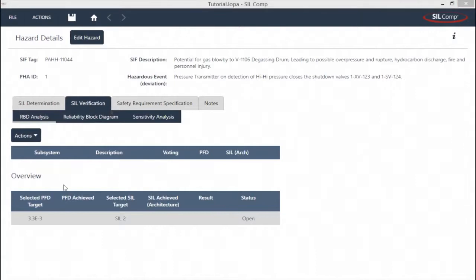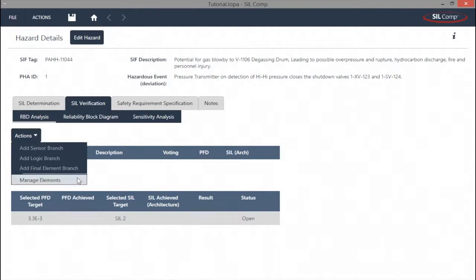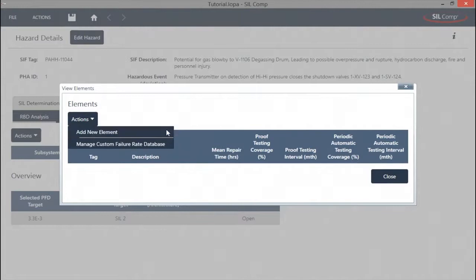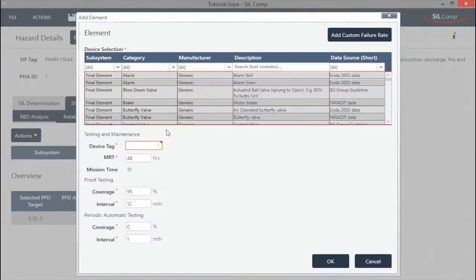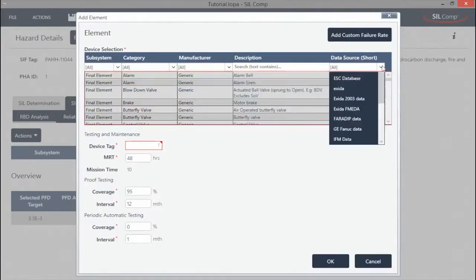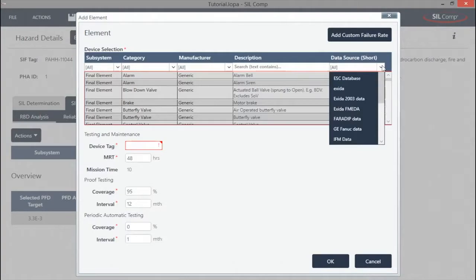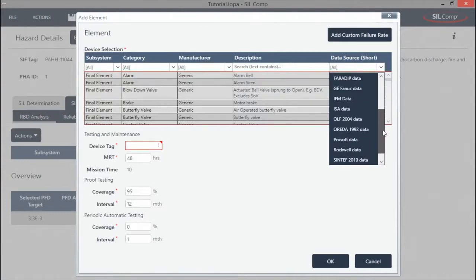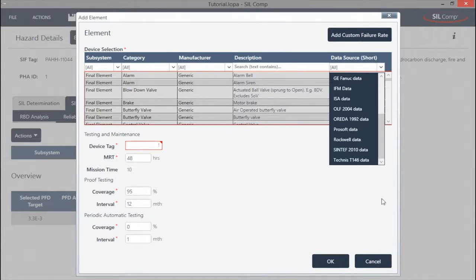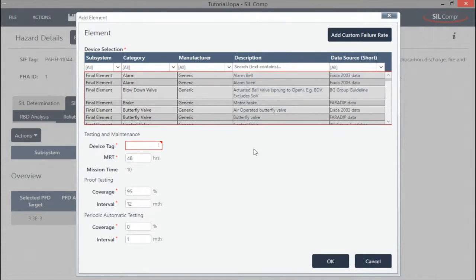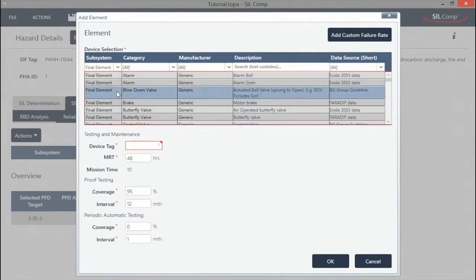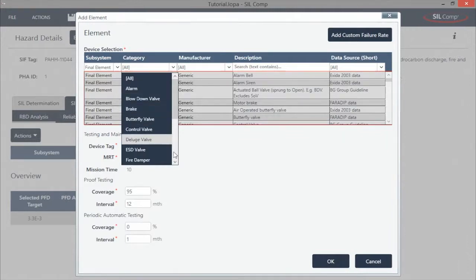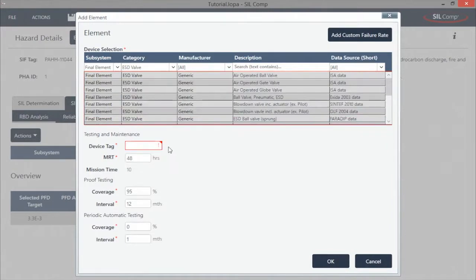SILCOMP incorporates an IEC 61508 certified SIL verification module, which facilitates the assessment of random hardware failures and architectural constraints elements. Elements can be configured using ESC's extensive master failure rate database, which incorporates failure rate data from sources such as Exida, Faradip, Sintef, OLF70, and various manufacturers and other relevant sources of data. Failure rate data is classified into subsystems, for example, final elements, and further subdivided into categories within those subsystems, for example, ball valve. This facilitates an easy time-saving search.